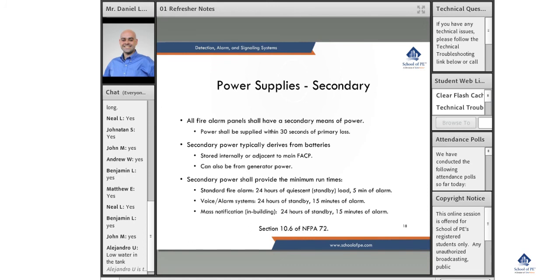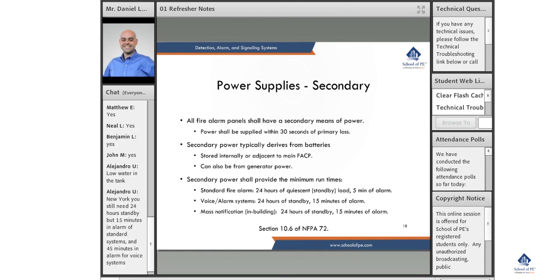The system has different demands depending on whether it's operating or not. Your speaker strobe is going to draw a lot more power flashing a light and buzzing a horn than just sitting there sending a signal that it's okay back to the fire alarm panel. Your voice alarm EVAC system is 24 hours and 15 minutes, and any mass notification system is also 24 hours and 15 minutes.